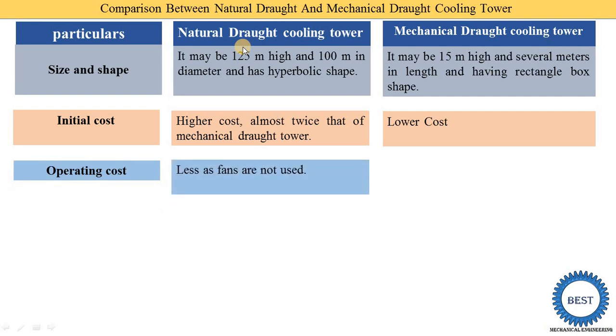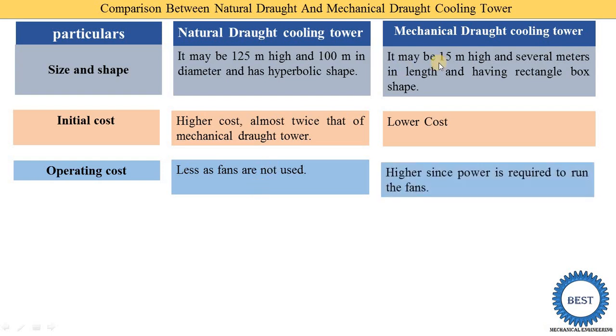The third difference is the operating cost — the cost required to operate the system. In a natural draft cooling tower, operating cost is less as fans are not used; we only need one pump to circulate the water from the condenser. In a mechanical draft cooling tower, operating cost is higher because power is required to run the fan, whether it is induced draft or forced draft, and electricity must be supplied to the fan.